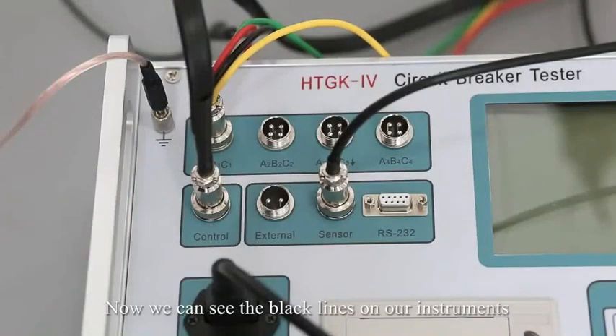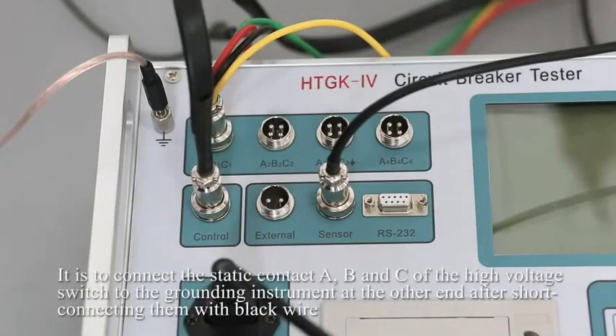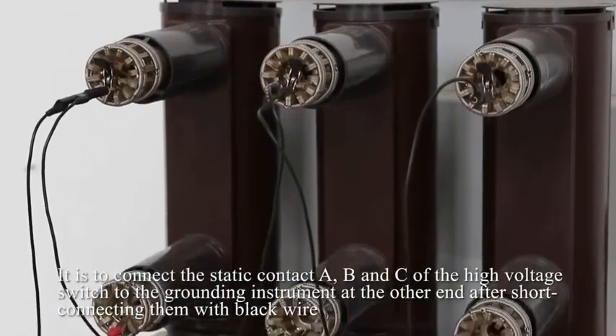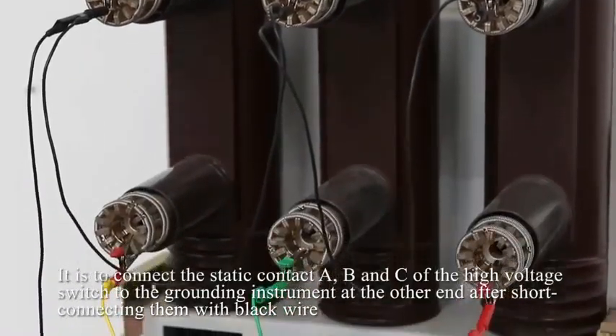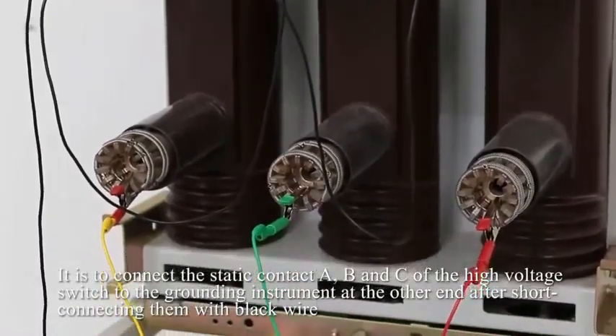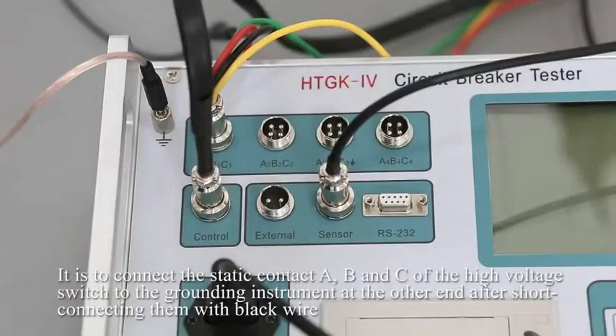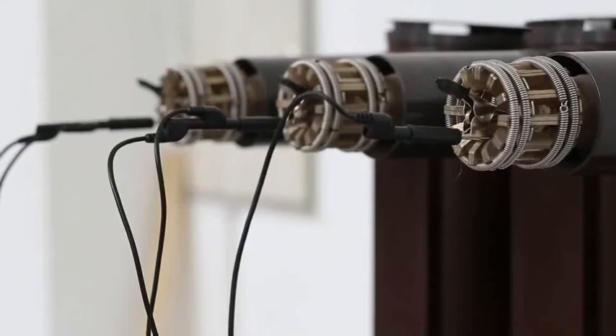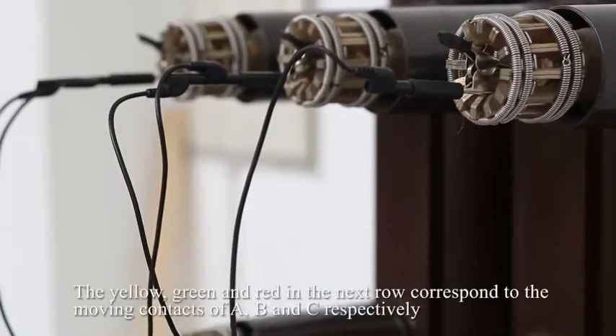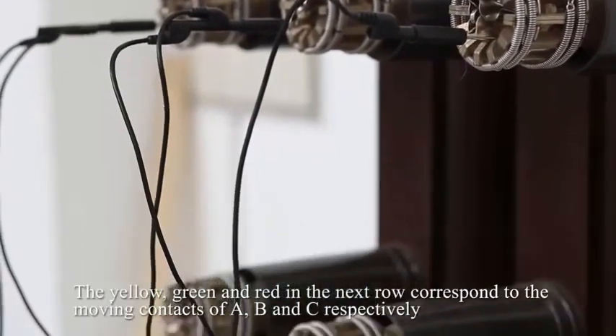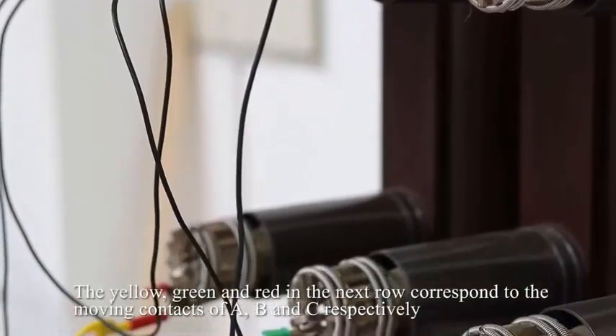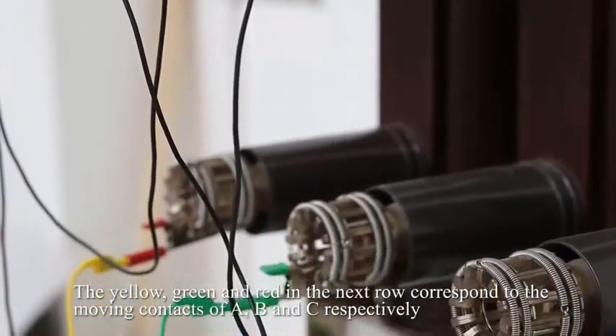Now we can see the black lines on our instrument. They connect the static contacts A, B, and C of the high voltage switch to the grounding instrument at the other end, after short connecting them with black wire. The yellow, green, and red in the next row correspond to the moving contacts of A, B, and C respectively.